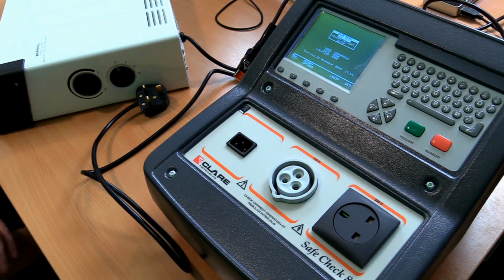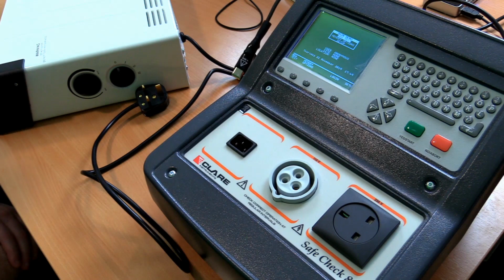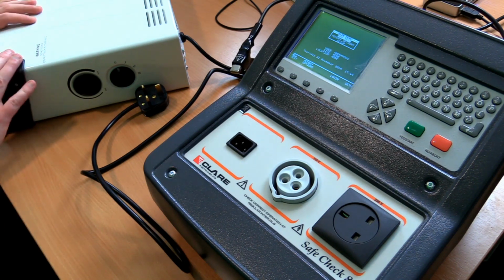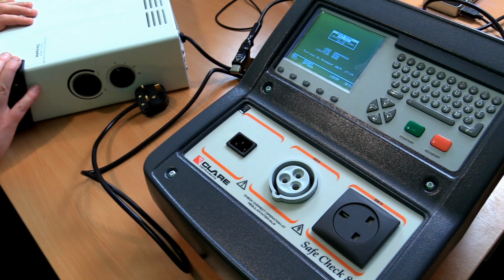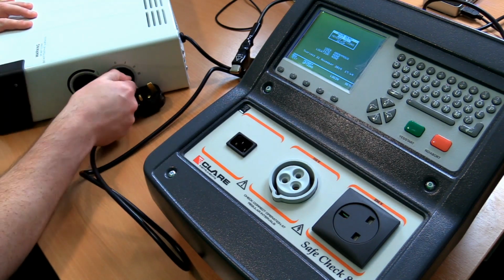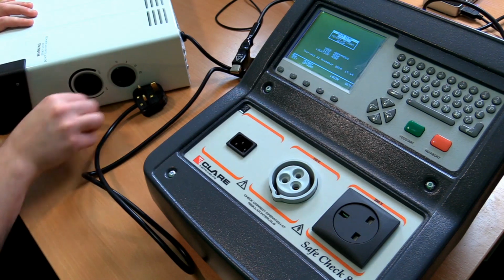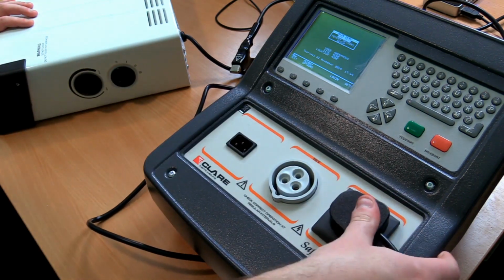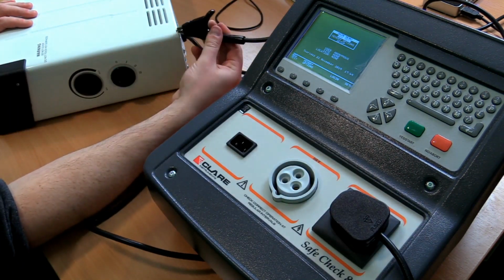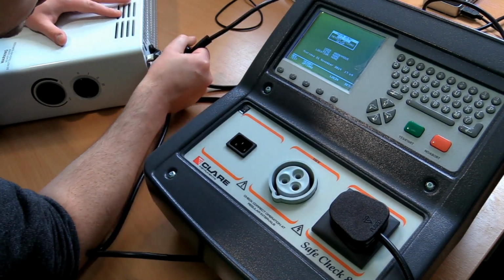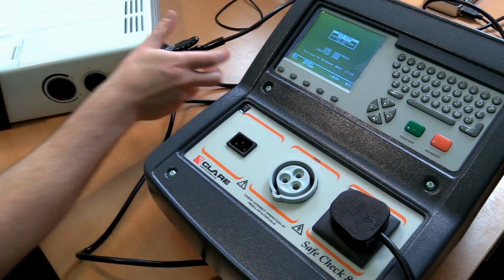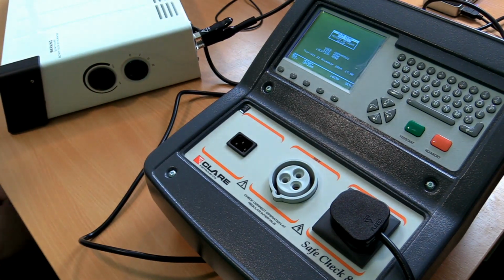So we've seen the insulation resistance test in that little animated diagram there. We're going to see what it looks like in the real world. We're going to use this little heater and test the insulation of the heater. So we're going to turn it on, make sure it's turned on for this test, turn it up to max and plug it in. We're also going to attach the earth bond clip to check the earth continuity to make sure that it's safe to actually do the insulation resistance test.